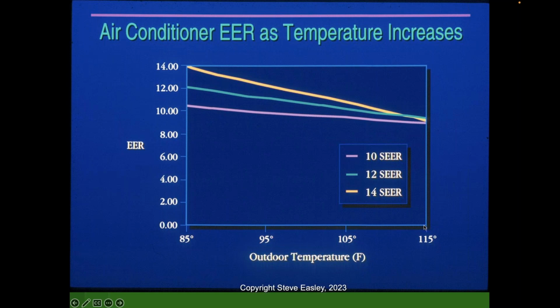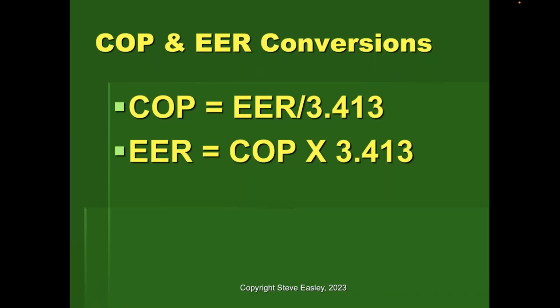So what I'm saying is that the seasonal energy efficiency ratios, even SEER2, are based on getting some latent cooling capacity out of dehumidifying the air like we have out in the Midwest and out east. But in the West, where it's so dry, we don't really get any additional cooling capacity from dehumidifying the air because the air is already so dry. So when you look at 105 to 115 degrees, look how all of the SEER 10, 12, and 14 come together. And so this is why in states like California, for example, Title 24, they require that manufacturers post their EER efficiency, so people will base their purchase decisions on real performance, not on this concept of SEER, which really doesn't apply. It's a national rating, but it really doesn't apply too much to the Southwest where it's very hot and very dry. Okay.